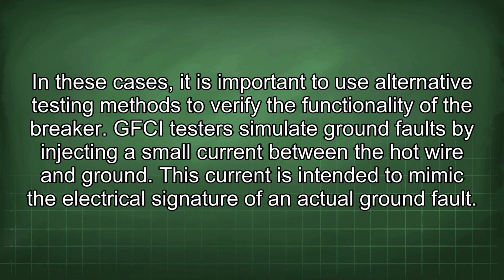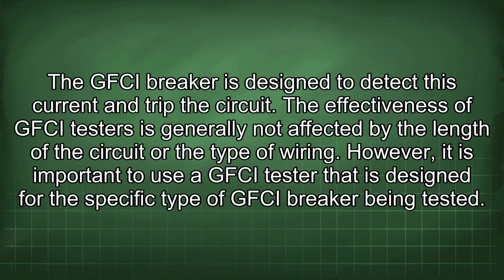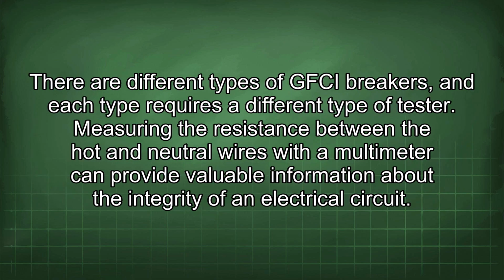GFCI testers simulate ground faults by injecting a small current between the hot wire and ground. This current is intended to mimic the electrical signature of an actual ground fault. The GFCI breaker is designed to detect this current and trip the circuit. The effectiveness of GFCI testers is generally not affected by the length of the circuit or the type of wiring. However, it is important to use a GFCI tester that is designed for the specific type of GFCI breaker being tested. There are different types of GFCI breakers, and each type requires a different type of tester.